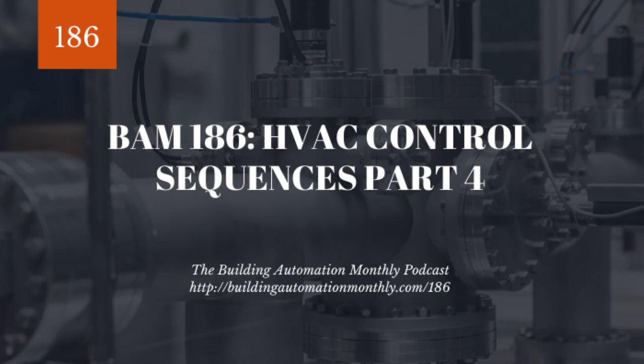airstream, because remember, with psychrometrics, we are going to already be at a pretty low amount of moisture as the temperature gets lower. So even a 30, 50, 60% relative humidity is going to have much less moisture at 0 degrees outdoor air than it is at 70 degrees outdoor air, just due to hotter air being able to contain more moisture content. So what's going to happen is we're going to have this preheat, and especially if we use steam and we heat it up really fast, one, we're going to want to have really tight control, 1/3, 2/3 valves, to make sure that we're controlling our steam and we're not overheating the airstream. But two, we're going to want to make sure that we are introducing humidity after this, because we're going to bring that temperature up, and most likely that relative humidity is going to drop substantially.